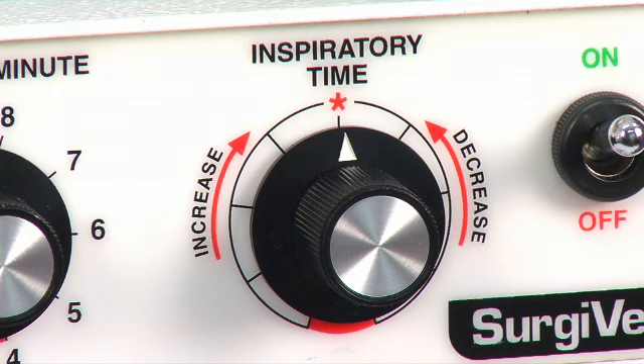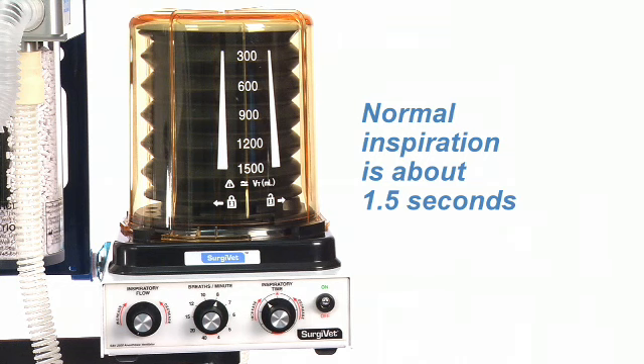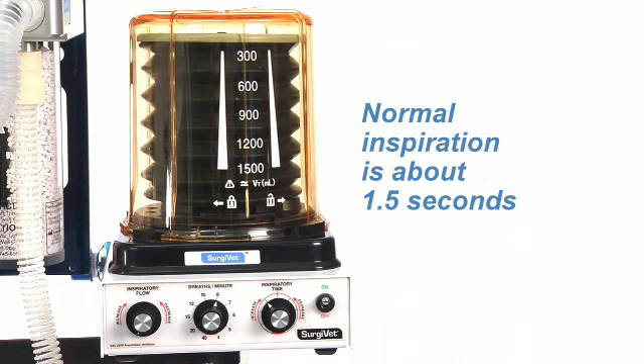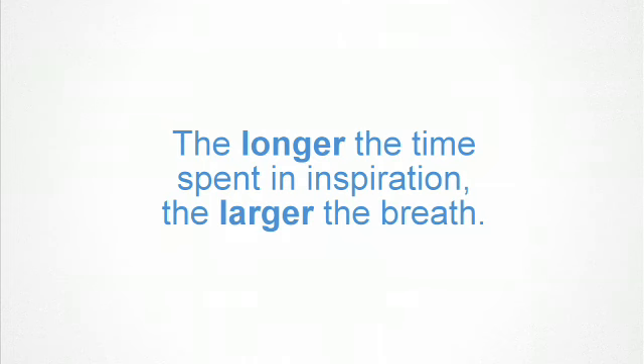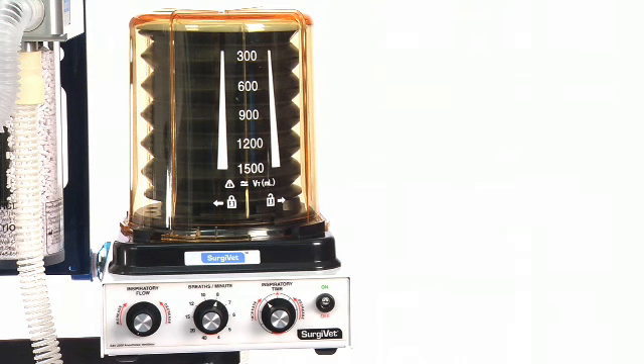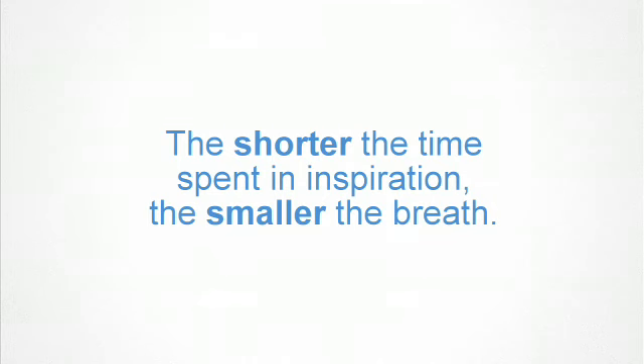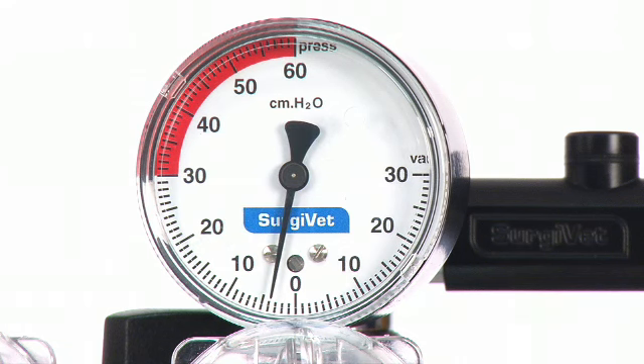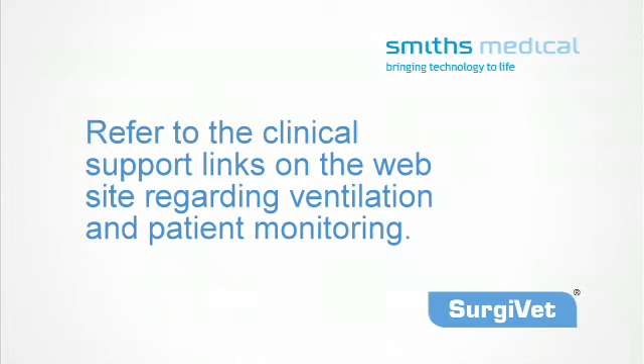The knob on the right controls the inspiratory time. Normal inspiration is about 1.5 seconds in length. The longer the time spent in inspiration, the larger the breath. The opposite is also true. The shorter the time spent in inspiration, the smaller the breath. Please note that it is strongly recommended to properly monitor patient pressure and end-tidal CO2 when using the ventilator. Please refer to the clinical support links available on the website regarding ventilation and patient monitoring.